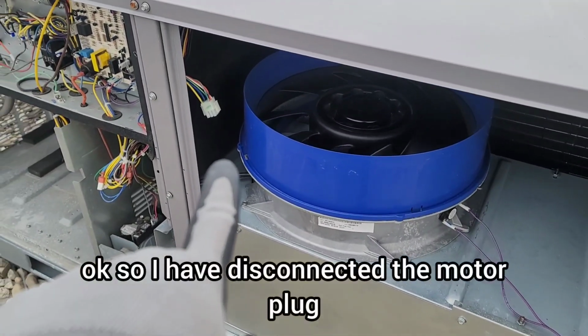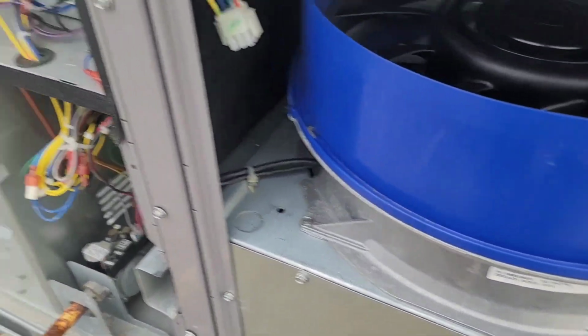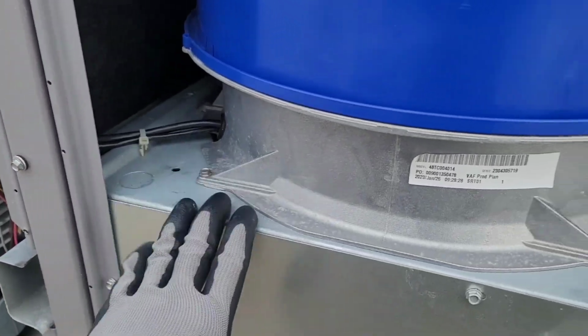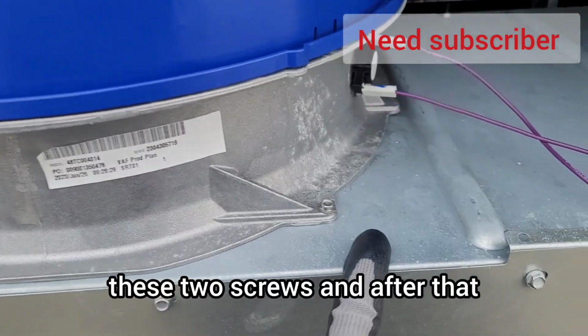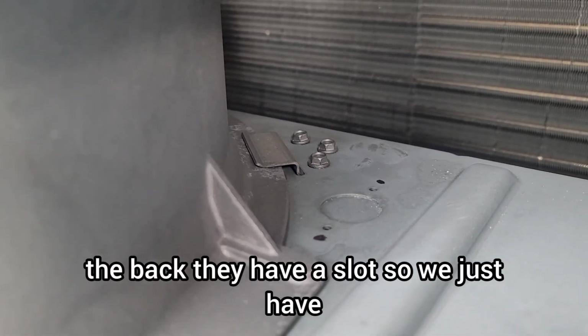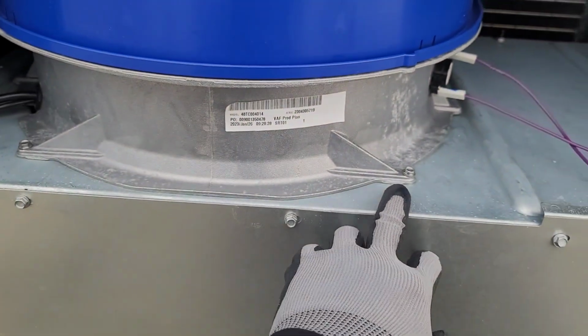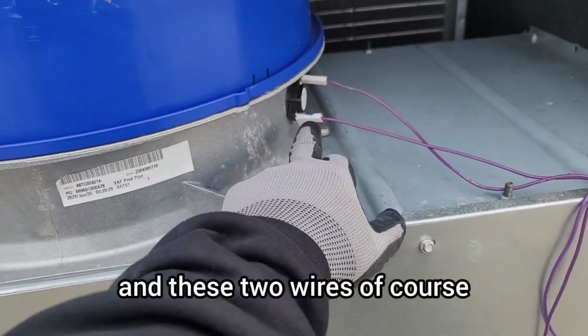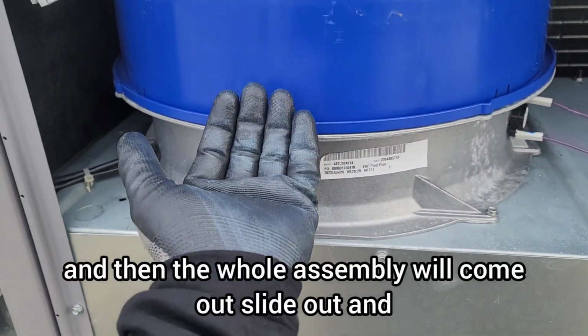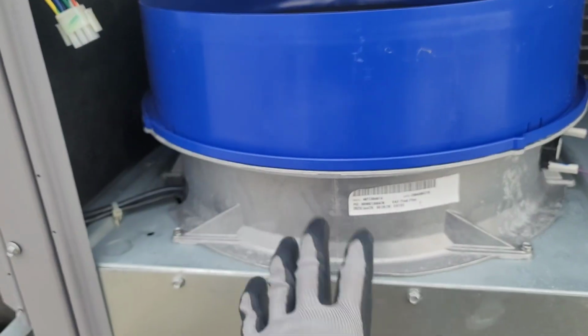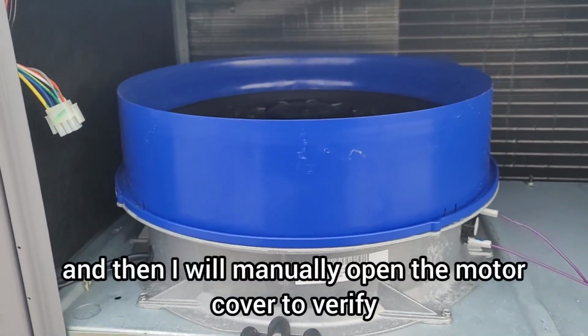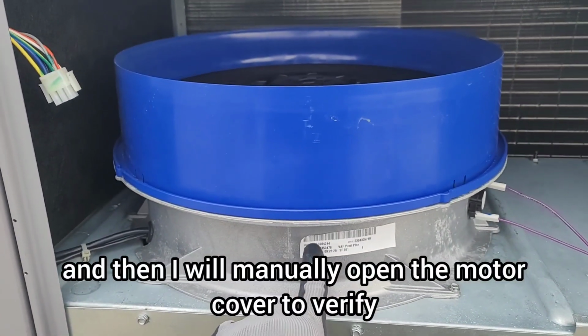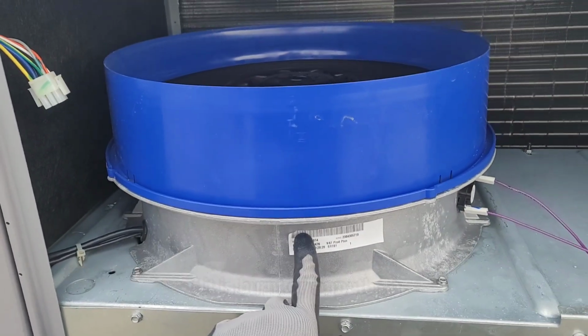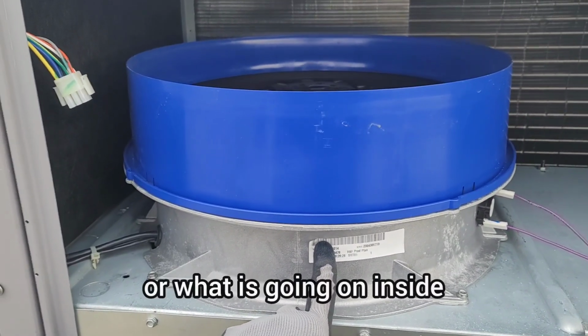Okay, so I have disconnected the motor plug, disconnected the power, of course. So let's see how it is mounted. I can see these two screws, and at the back they have a slot. So we just have to remove these two screws and these two wires, of course, and then the whole assembly will slide out, and then I will manually open the motor cover to verify if it is burnt or what is going on inside.